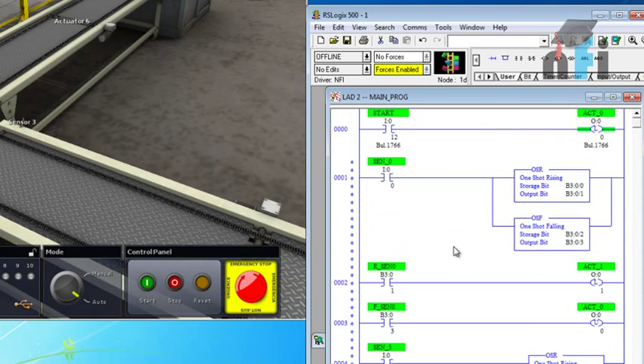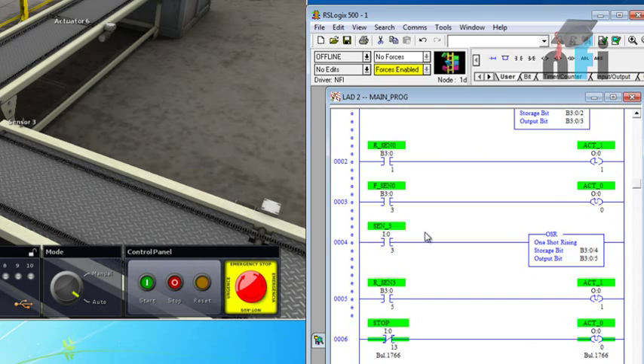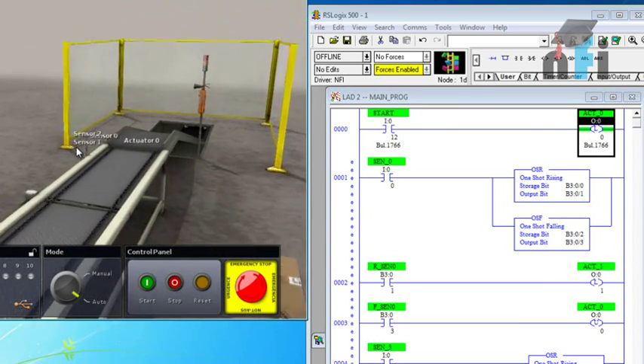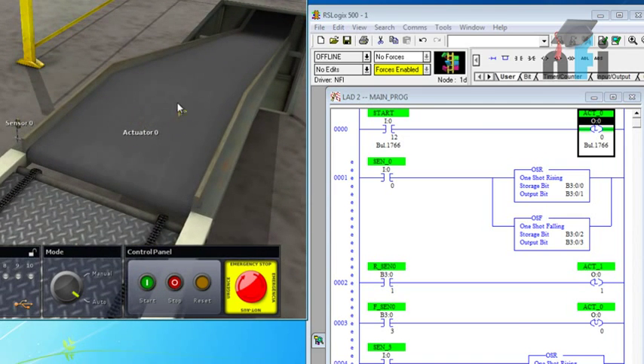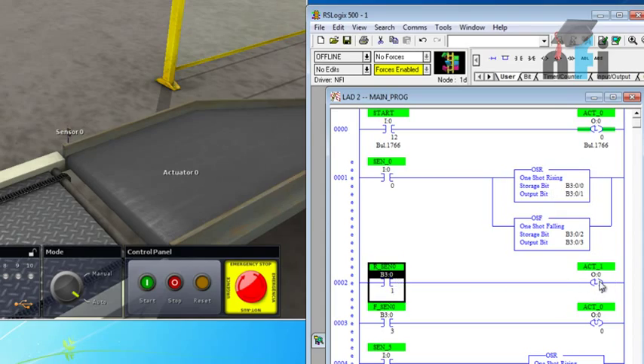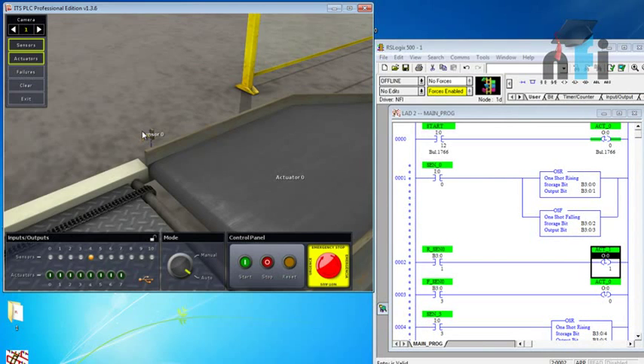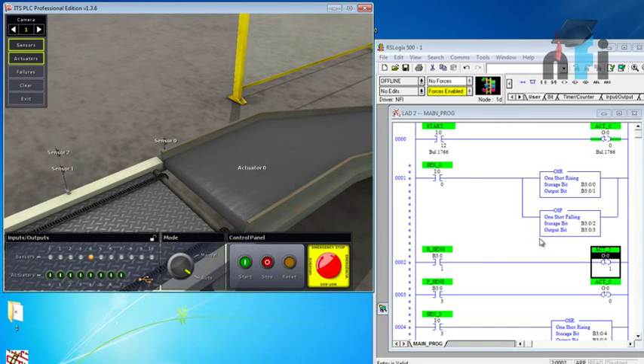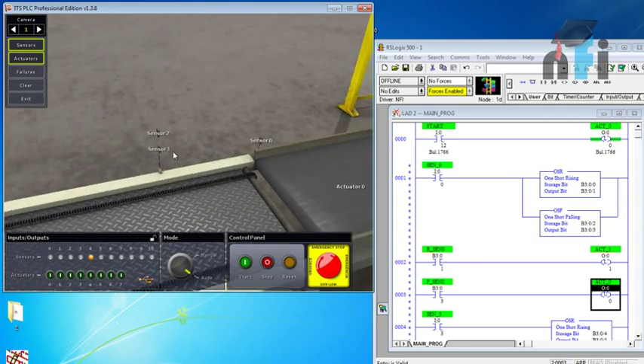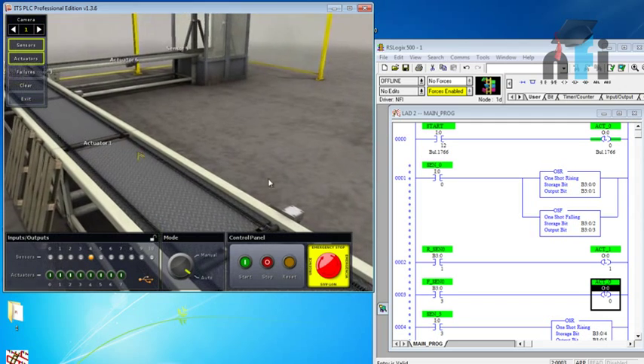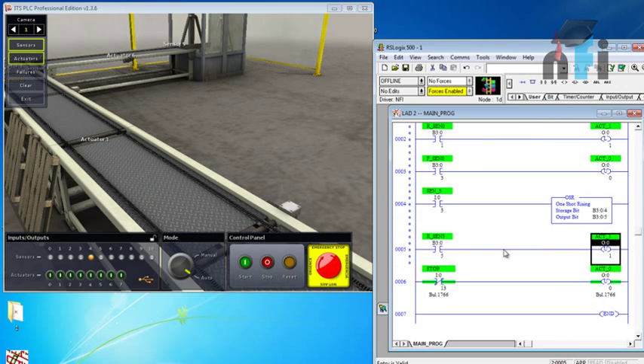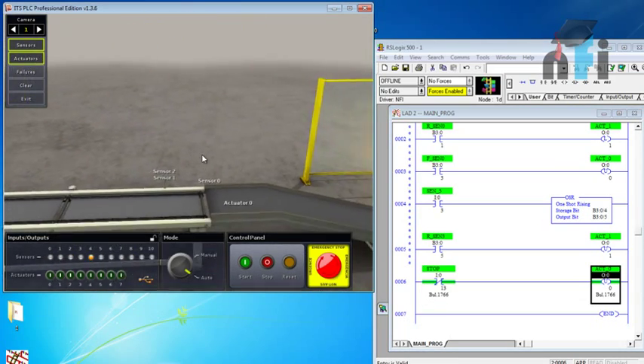Using output bit 5, take a rung with a contact for rising sensor three, then unlatch actuator one with the same address. To summarize: the start button latches actuator zero; when the box comes to sensor zero, the rising edge latches actuator one; when it leaves sensor zero, the falling edge unlatches actuator zero; when it reaches sensor three, the rising edge unlatches actuator one. There is also a stop button to turn off the actuator.